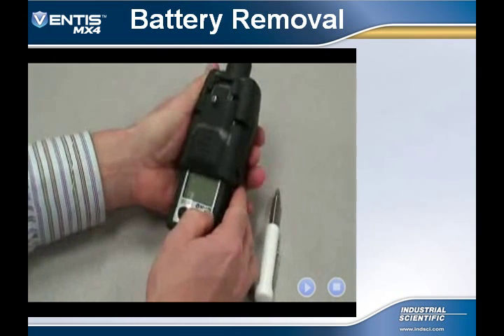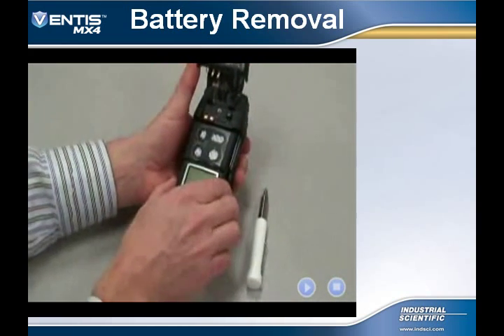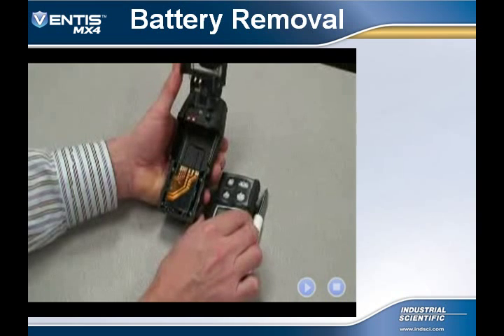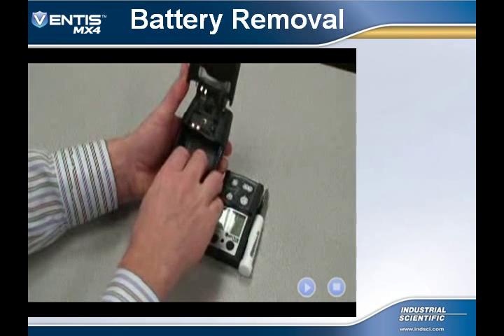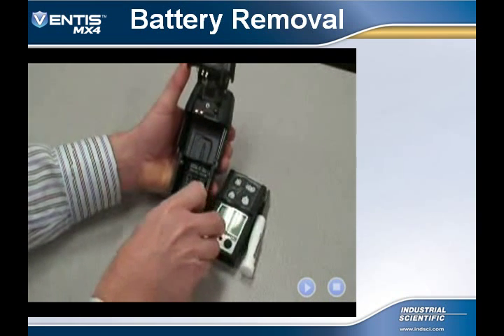Rotate the instrument to its front again, slide the front pump door forward, and lift to expose the instrument. Remove the instrument from the pump housing and expose the battery pack inside.